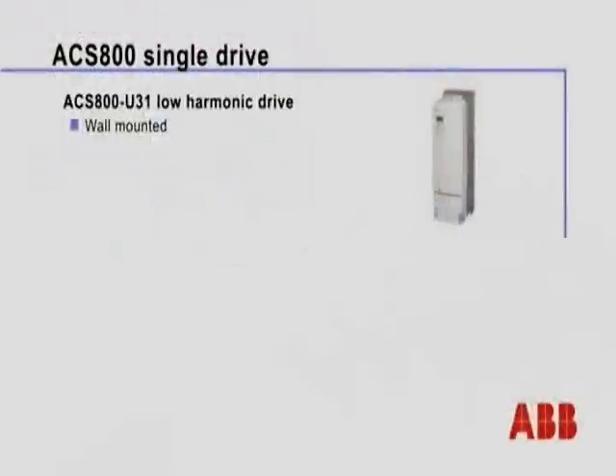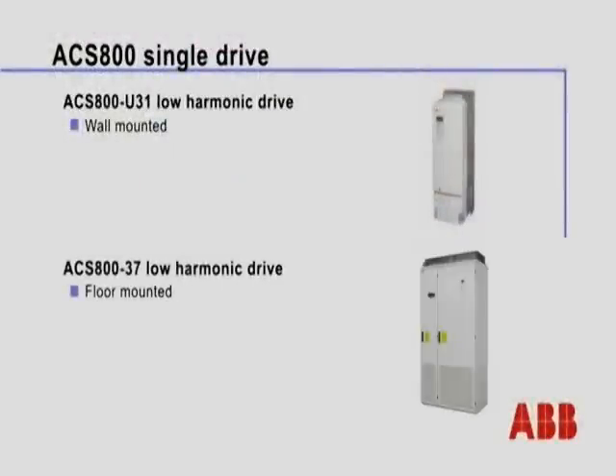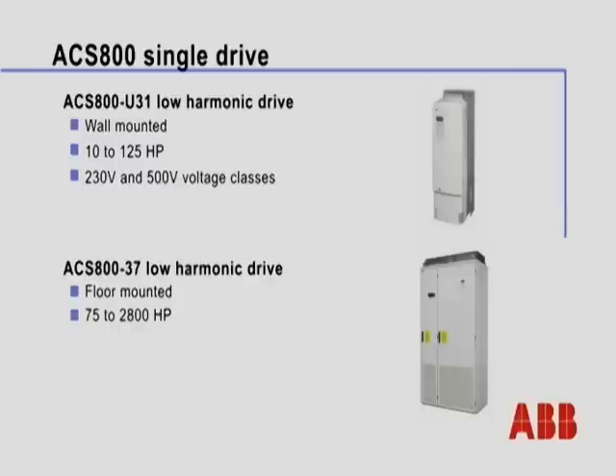Now that I've told you a little bit about how ABB does it, let me tell you a little bit about the ABB product offering. The ACS800 ULH is available in two varieties, one a wall mount version, the other a freestanding or cabinet version. The wall mount is available in horsepowers from 10 horsepower up through 125 horsepower and voltages of both 230 volt and 500 volt. In the freestanding units, we range from 75 horsepower all the way through 2800 horsepower. These voltages are from 500 volt class and 690 volt class.